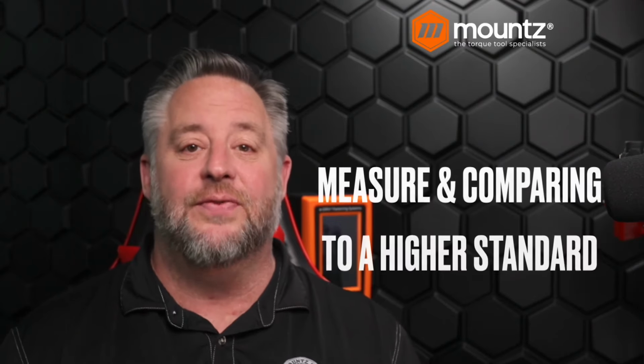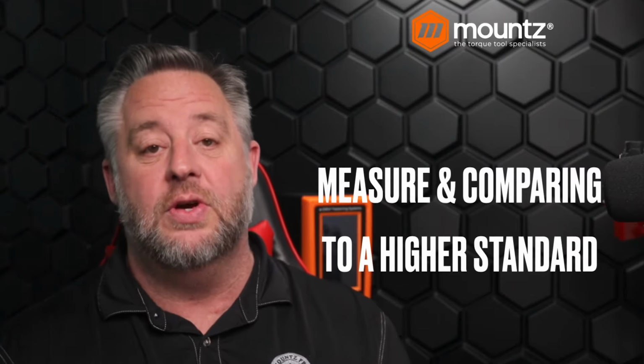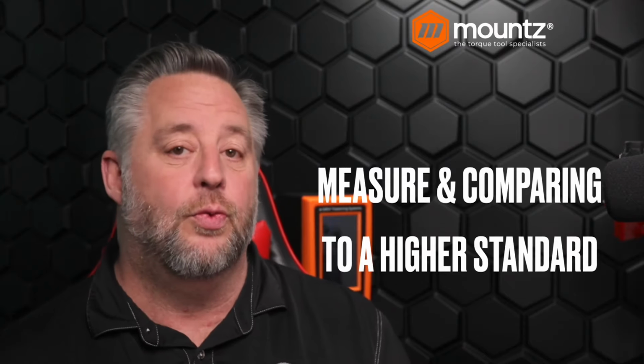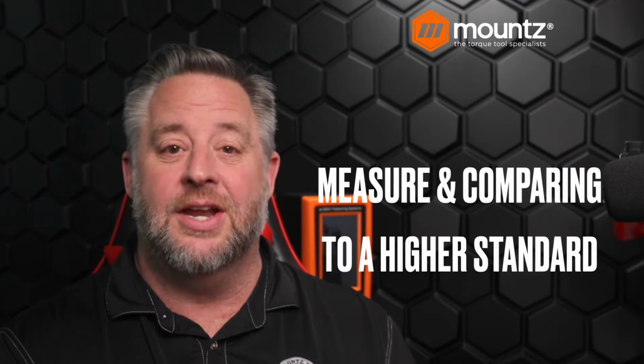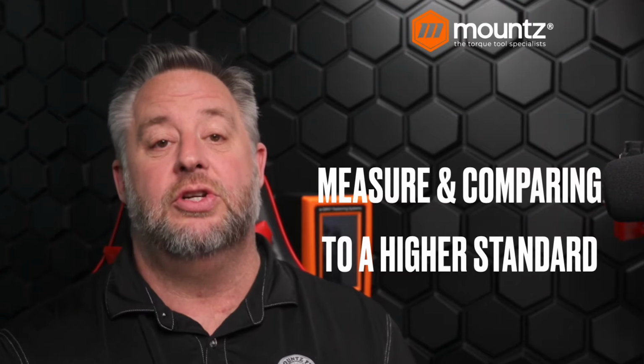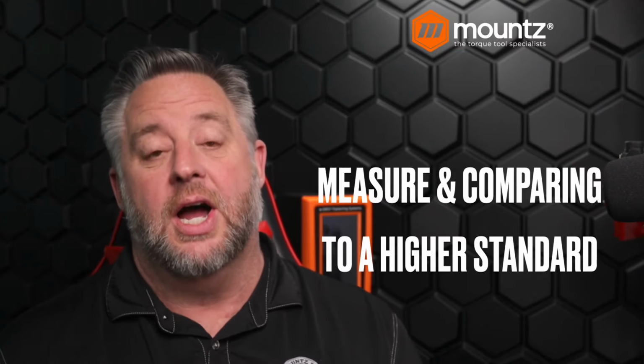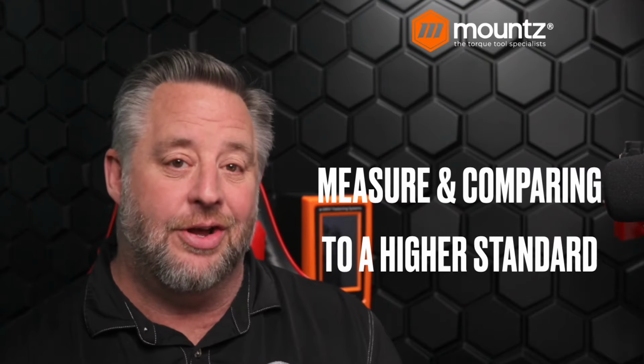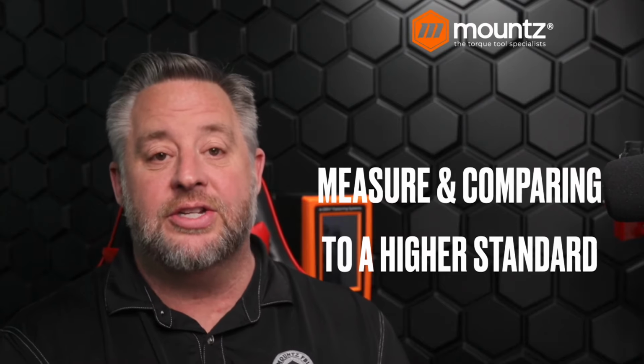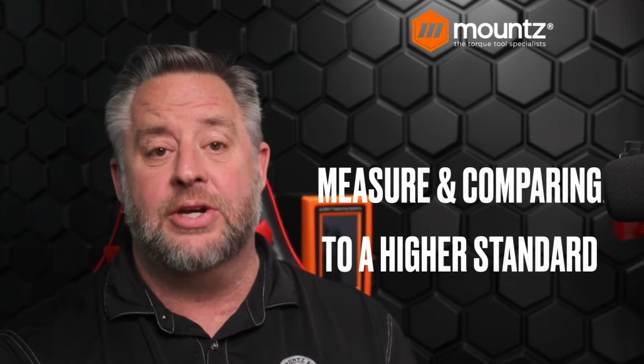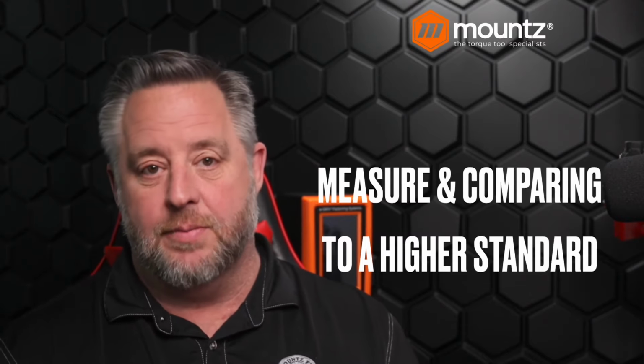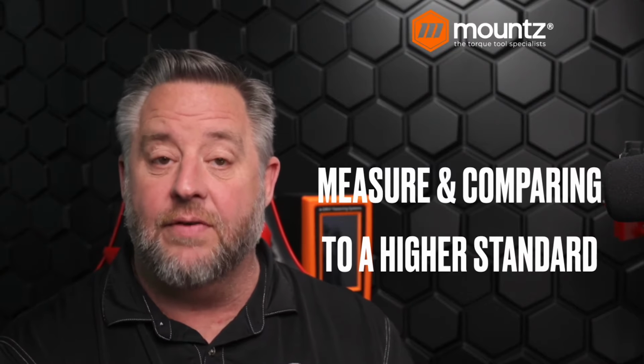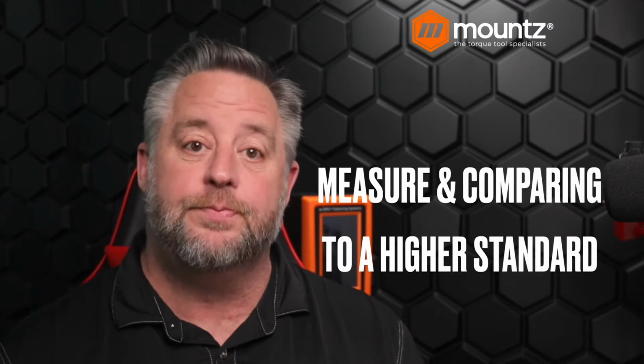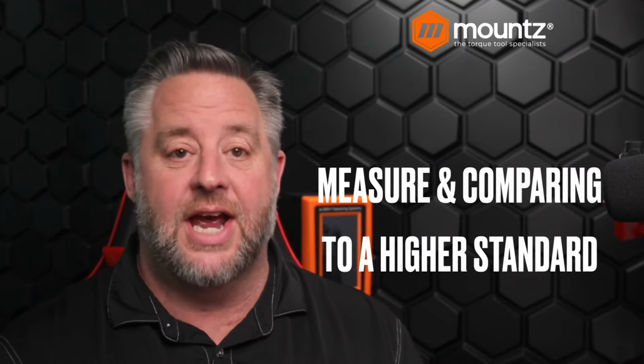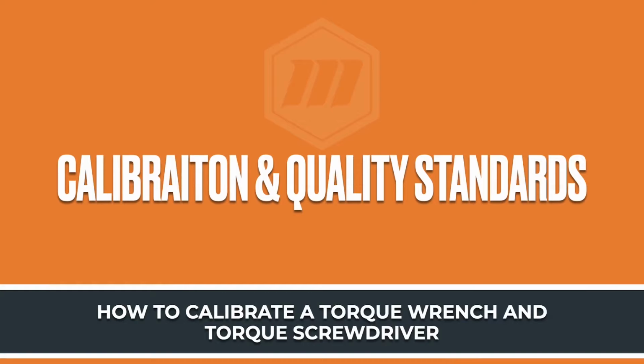Now, there are a number of different components that go into the actual torque calibration process. But when we do the actual process itself, we are measuring the device that we're using and comparing it to another device, and the one that we are comparing with must have a higher standard of accuracy than what we are measuring. In this case, if we're dealing with a torque tool and we are measuring that torque tool on a torque analyzer, that analyzer is going to have a much greater accuracy statement than the actual tool itself. So we can make sure that we are well within the tolerance of the analyzer and the tool as we're measuring the torque calibration. Now, that standard may be different for different things, but in our case, it's typically a 4-to-1 ratio.